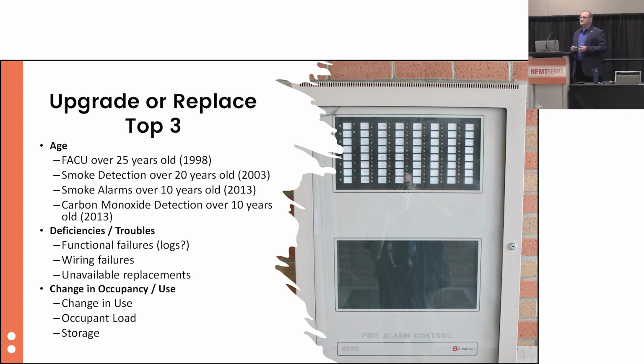Carbon monoxide is an increasing danger. By the 2024 edition of the IBC codes, you'll see carbon monoxide requirements in every major occupancy group, A, E, all of the public occupancy groups. So we're going to see a huge increase in carbon monoxide detection requirements. It's very dangerous anytime you're dealing with fossil fuel burning appliances, hot water heaters, washers, dryers, dishwashers, HVAC equipment. All kinds of things are creating carbon monoxide poisoning all around this country each and every day.